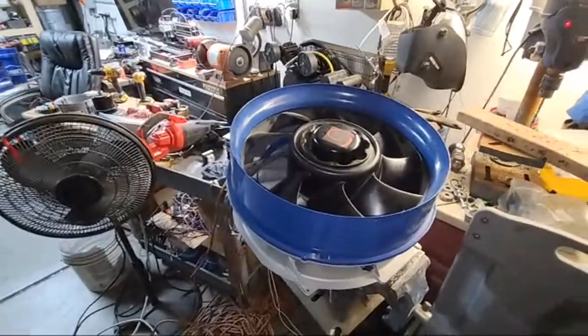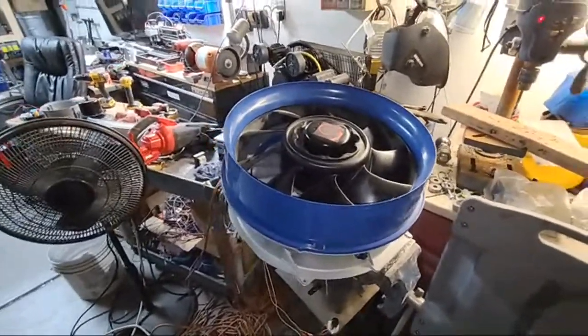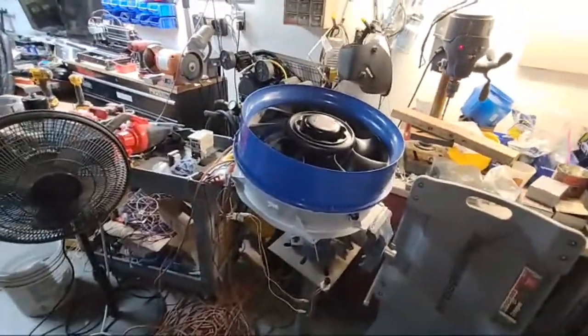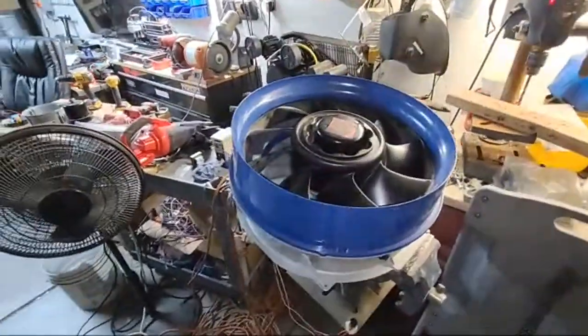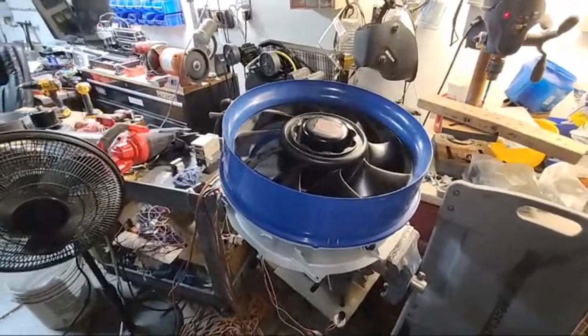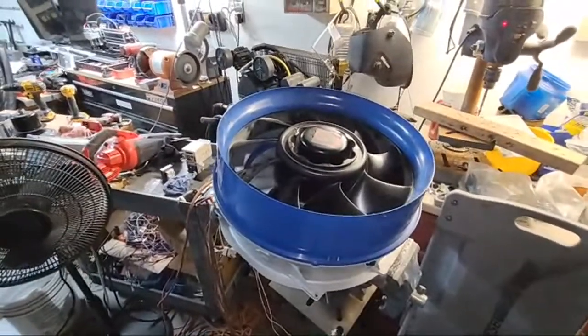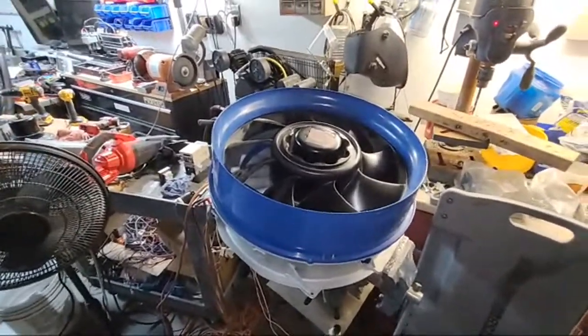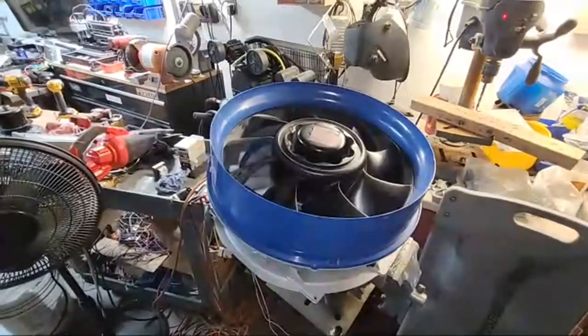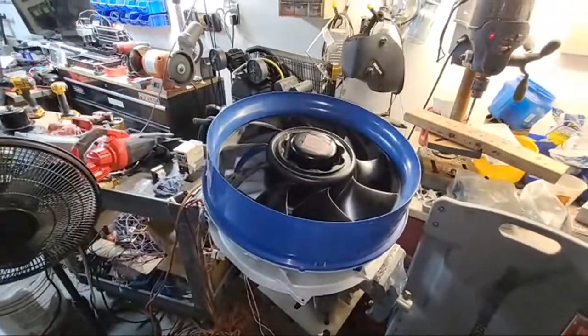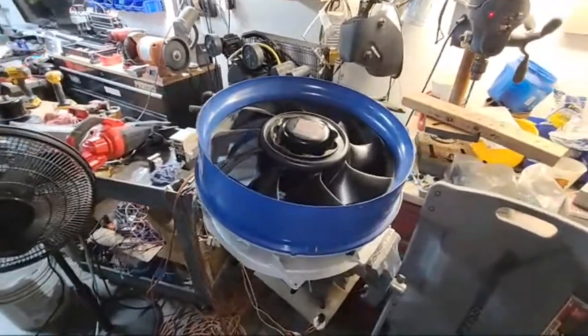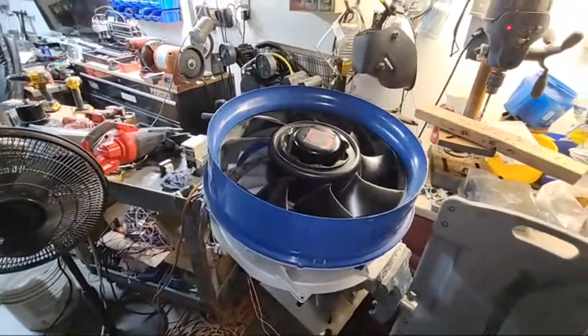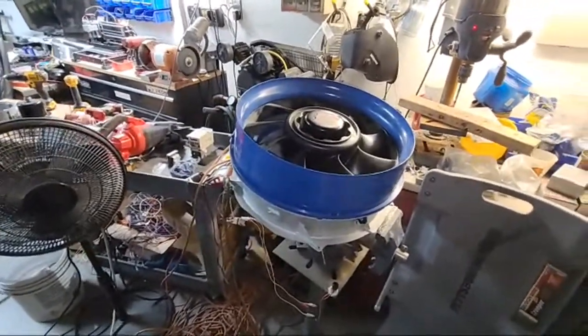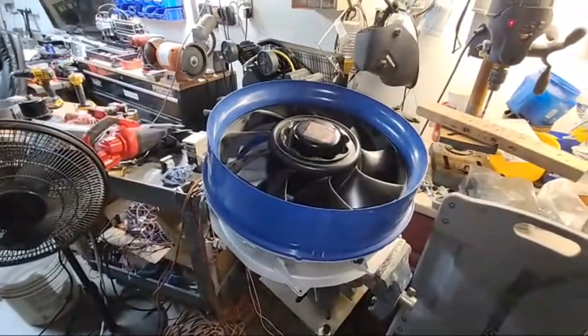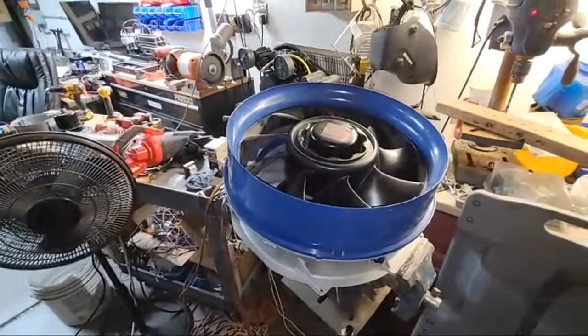It shouldn't matter what climate you're in, as long as the water had the right gallons per minute, 80 degrees, whatever. But then on the Trane Precedent outside rooftop units, where it's hot, and it's hotter on the roof than it is on the ground, I had to pull out 4 or 5 ounces out of some units. Same thing, pulled out just a little bit, didn't lose my split temperature, and it stopped the high pressure trips. But other than that, they're efficient.